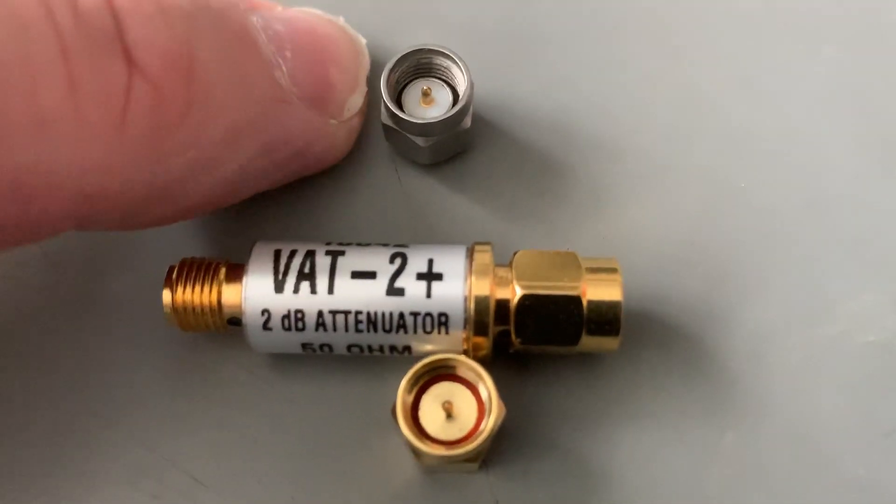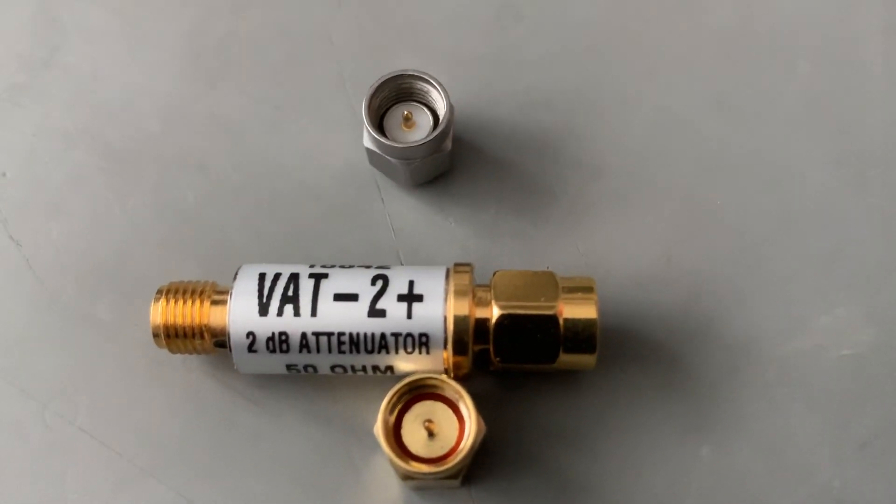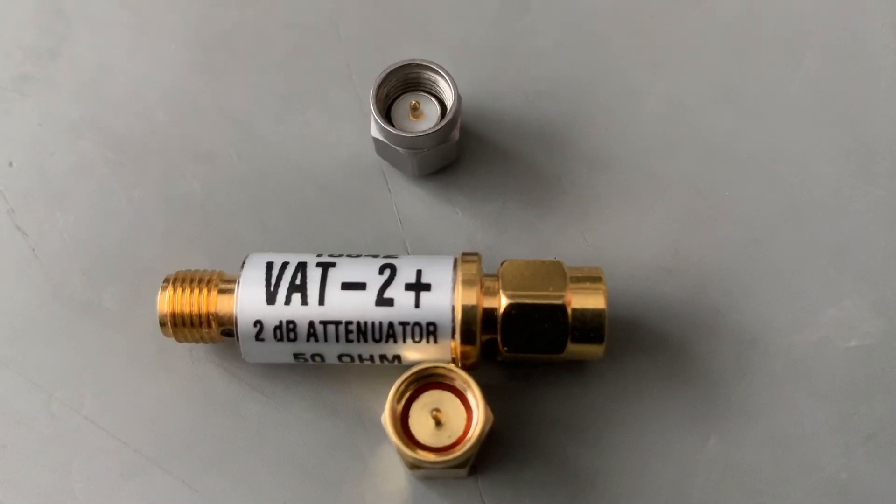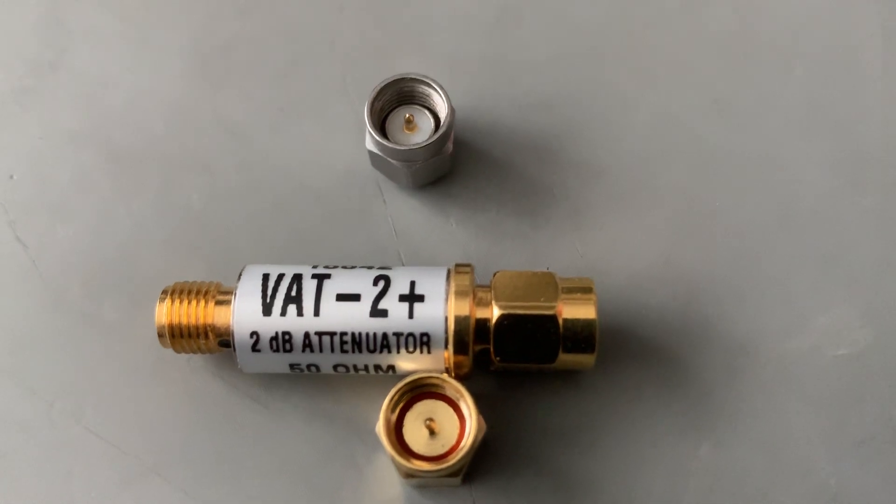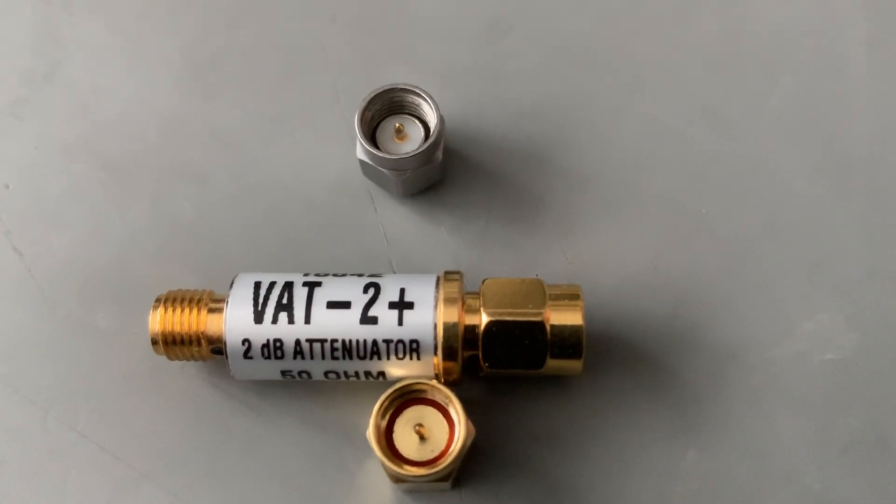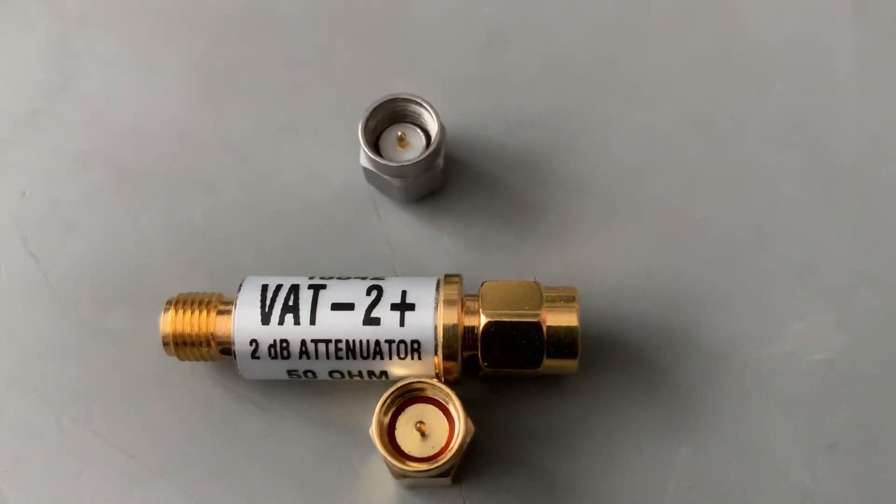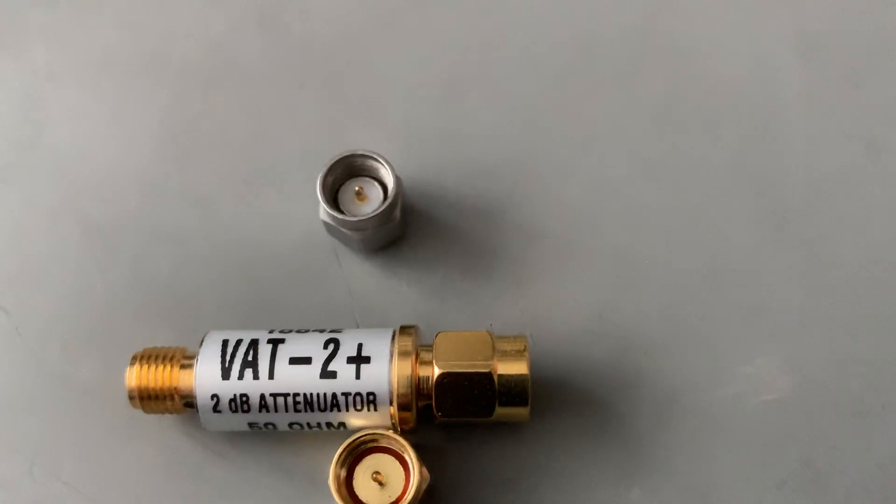At the top we do have a load but I'm not going to use that during the calibration. We've got no open standard, we've just got a short and an attenuator, and we're now going to try the most silly calibration and we'll see that we'll get excellent looking results.